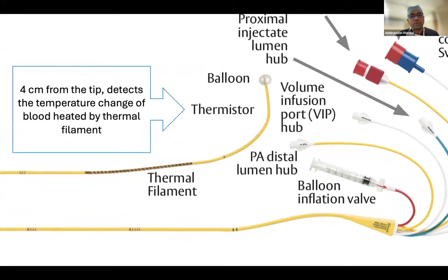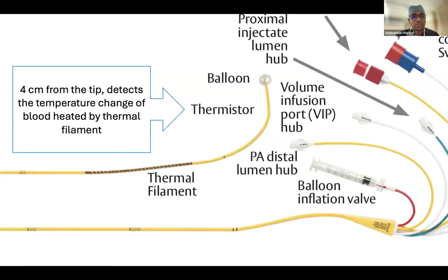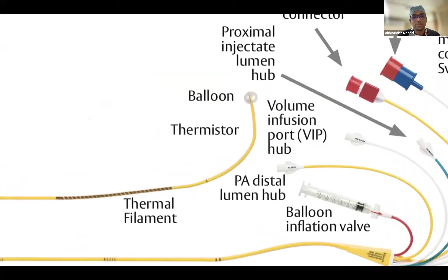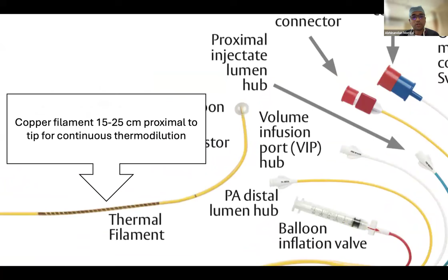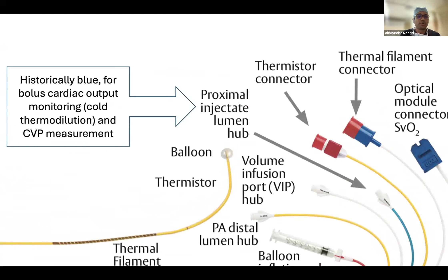At 4 centimeters from the tip, there is a thermistor, and also there is a thermal filament over 15 to 25 centimeters proximal to the tip for the continuous thermodilution method. And another thing, there is a proximal injectate lumen hub that was previously used for bolus cardiac output monitoring, that is bolus thermodilution, and CVP measurements.